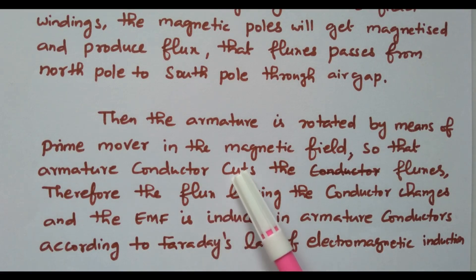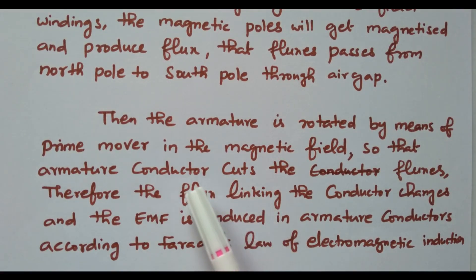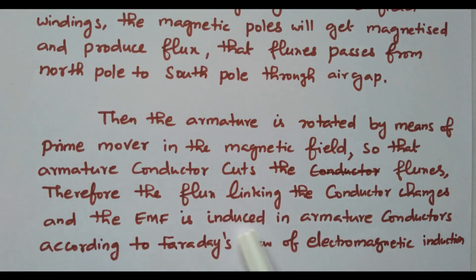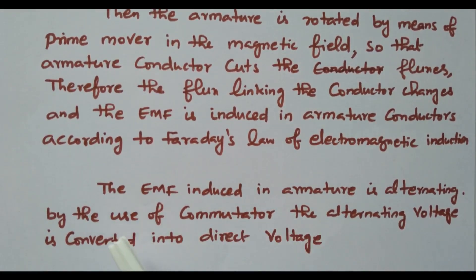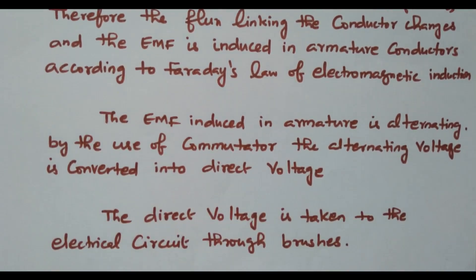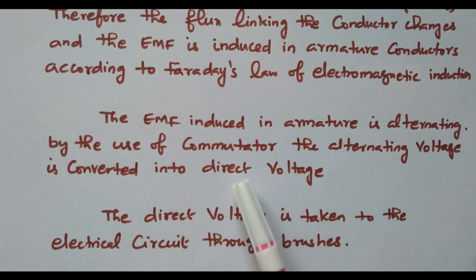The armature is rotated in an already available magnetic field, so the armature conductors cut the magnetic flux. Due to the rate of change of flux, EMF is induced based on Faraday's law of electromagnetic induction. The EMF induced in the armature is alternating. By the use of a commutator, the alternating voltage is converted into direct voltage. The direct voltage is taken to the electrical circuit through the brushes. The commutator collects the current and converts it into direct current; it is collected through the brushes.